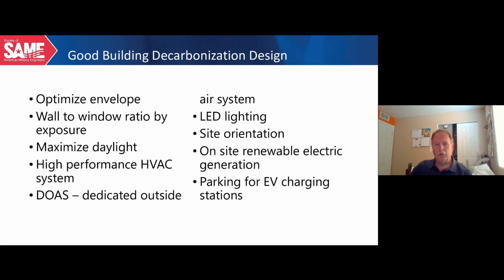LED lighting. With LED lighting, we're able to get lighting levels down to somewhere around 0.2 to 0.3, maybe as high as 0.4 watts per square foot, which is way better. When I started in this industry way back in 1974, it wasn't uncommon that we would see lighting levels in commercial office space at 2 to 3 watts a square foot. So we're 1/10 of that number with LED.